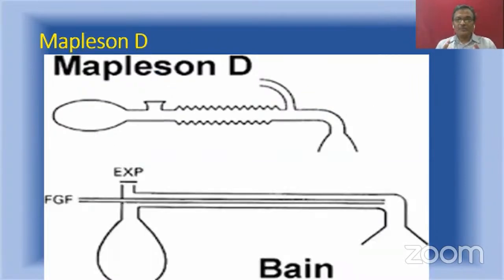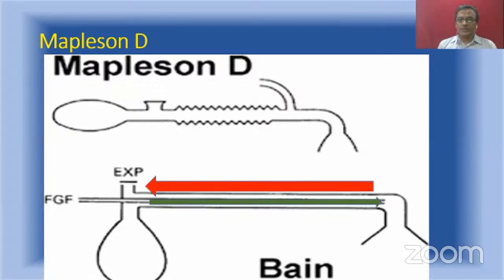Now I will show you a modified Mapleson D. I said this modification was done by Bain and Spoerel. Here, look at this fresh gas tube. Instead of joining from outside, the tube enters into the circuit and moves inside and finally reaches the patient end. The fresh gas moves in towards the patient while the expired gas moves in the opposite direction in the outer tube. That means these two flows are in opposite directions but in the same axis.